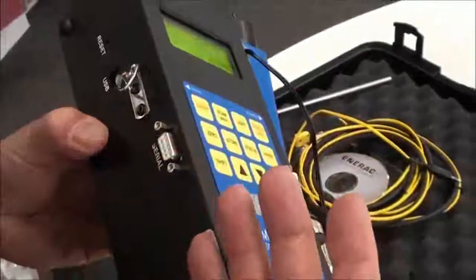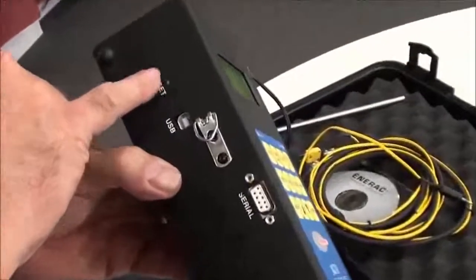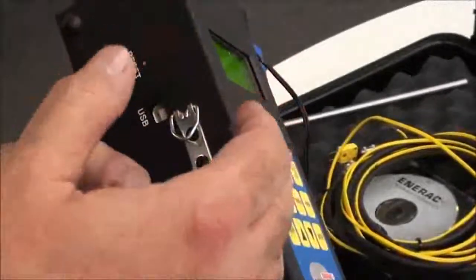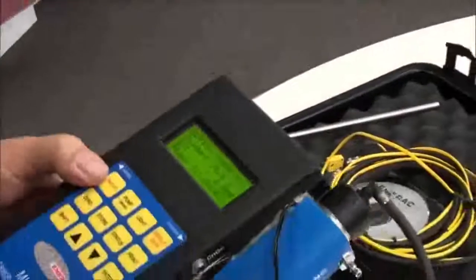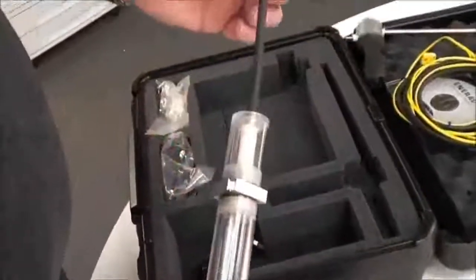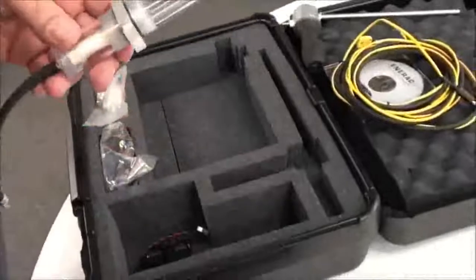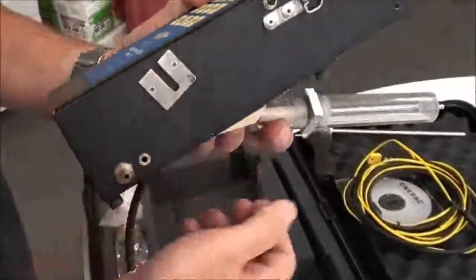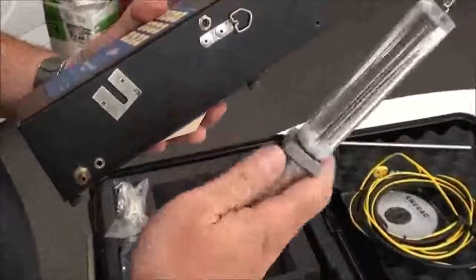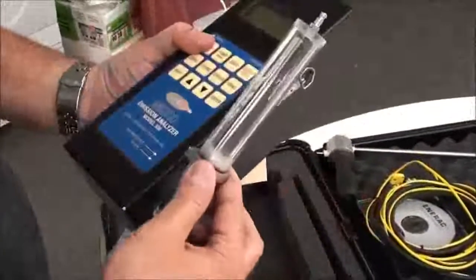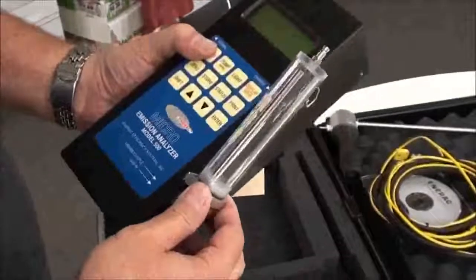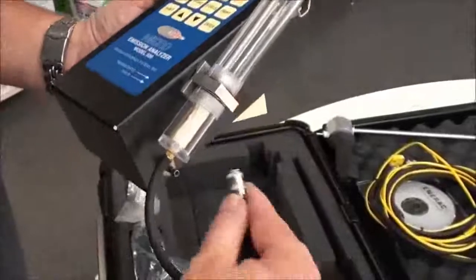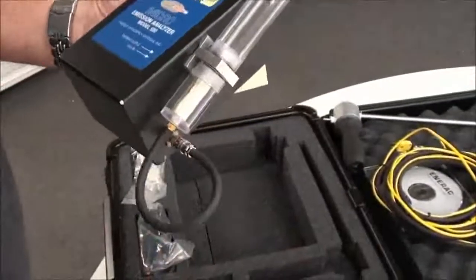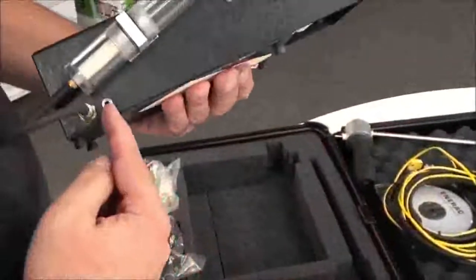In the event your batteries go dead, you recharge it. Sometimes the microprocessor won't turn on when you hit the on button. You may have to just hit the reset button. After you hit the reset button, or if the batteries go dead and you recharge them, you'll have to reset your time and date. Just keep that in mind. One more thing. If you have a water trap instead of the cooler, the water trap has a dovetail mount on the side of the unit, and there's a corresponding dovetail cut into the aluminum piece here. That just simply slides in, like so. It mounts on the side, then you take your hose and plug it into the bottom. At that point, you'll connect the rest of the hose and the thermocouple down here.